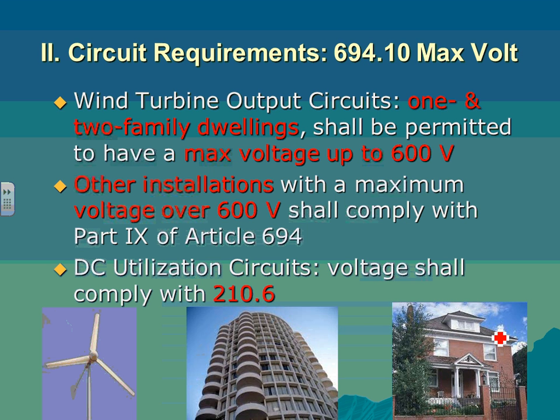DC utilization circuits, voltage shall comply with 210.6. If you decide, in the house, to utilize the circuit at the DC level or actually at the AC level, then you can't bring 600 volt and burn a light inside the house, right? There's a limitation on the voltage of branch circuits that you can burn a light on. You can go 600 in tunnels for branch circuits. So if you go there, 210.6, it gives you the limitation: can I burn a light at 600 volt in my house? No, you can't, even if you want to, code-wise.